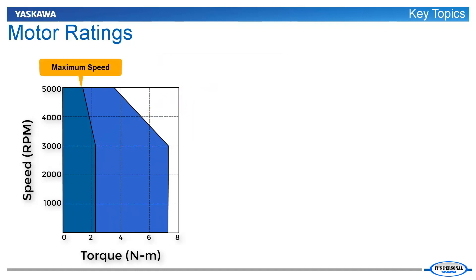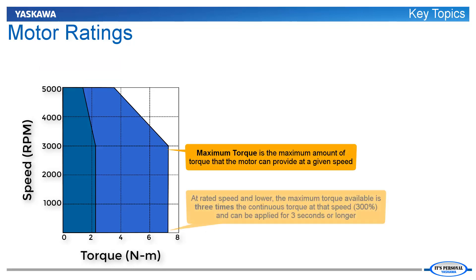The motor's maximum attainable speed is listed at the top of the speed-torque curve, and the motor's maximum torque is at the far right. The maximum torque available is generally three times the continuous torque and can be applied for three seconds or longer.